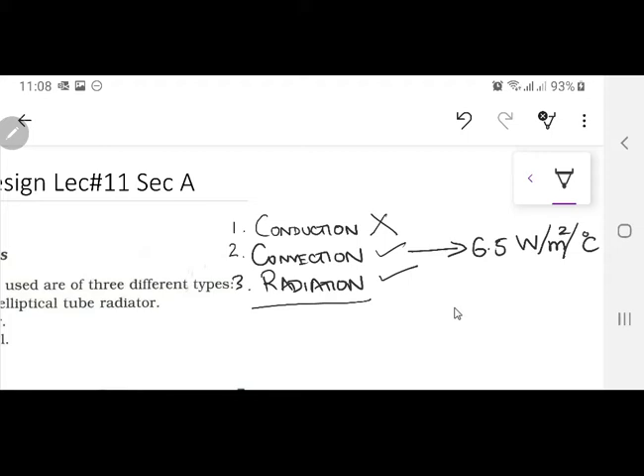So inside the transformer tank, whatever the convection rate is, you can dissipate 6.5 watts per meter square per degree centigrade from the convection of the oil inside the tank. The radiation has 6 watts per meter square per degree centigrade.